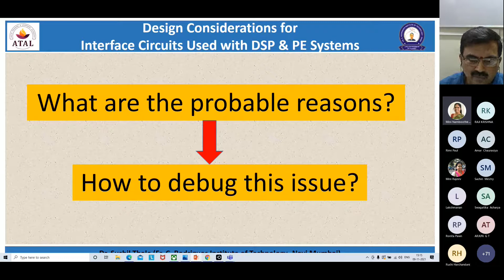So let me give you the overall picture. We felt the power electronic system was at fault. We also checked whether the DSP was an issue, since it wasn't a closed loop system — it was simply driving the SPWM to the inverter, and we observed this efficiency loss throughout the exercise. Changing the frequency from 10 kilohertz to 2 kilohertz showed an increase in efficiency, which is obvious, but that wasn't the way to solve the problem. The actual problem must have been something else. So what was that problem?